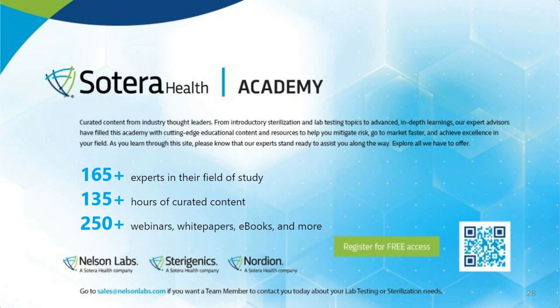Hi, this is Dr. Campbell. I'm happy to answer that question. So your particular device in question does fit into multiple different categorizations per ISO 10993 and also qualifies for categorization per ISO 18562. So those parts that are contacting the mouth would be considered that surface device mucosal membrane contact. For the inner airway, that would be your air VOC, and for your condensate that could be collected within the interior of that device, you would also need to conduct some sort of extractable or leachable study. You are also, based on this type of device, an externally communicating tissue contact device, so would be required per ISO 10993 to address the biological endpoints for that categorization as well.